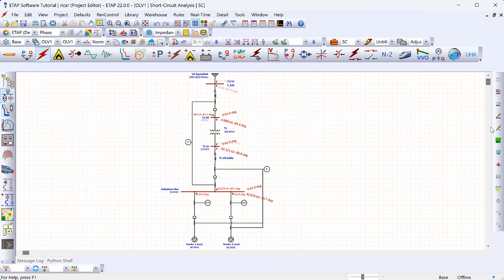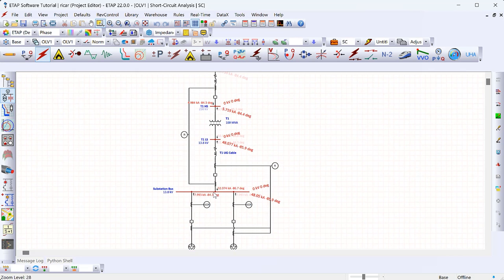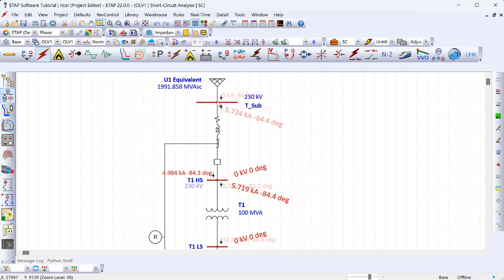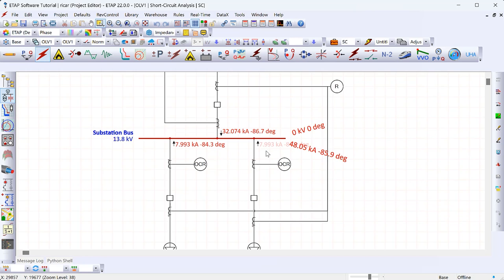You can have maximum and minimum values, but for the most part you'll be using maximum values. This gives us the fault current levels for every bus in the model. Zooming in on the substation bus, the total fault current for a fault at this bus is 48 kA. ETAP displays current in kA. It also shows the contribution from each side: 32 kA from the transformer (from the utility equivalent) and about 8 kA back-feed from the induction motors, which all adds up to 48 kA.